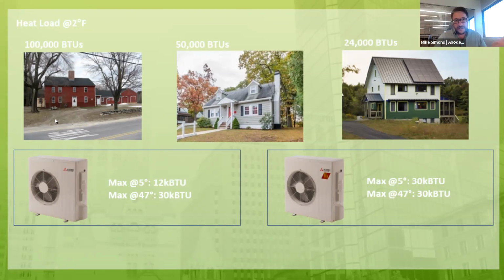So if I were to try and heat up this leaky farmhouse with this non-cold climate heat pump, I would need 9 outdoor units just to make up for the amount of energy that it's losing. If I'm looking at the heat pump on the bottom right-hand side, I would see that this heat pump, no matter if it's single digits or 47 degrees outside, can still supply 30,000 BTUs per hour. So with the leaky farmhouse, for example, maybe I would be able to get by with 3 or 4 heat pumps to power this really leaky, inefficient home.